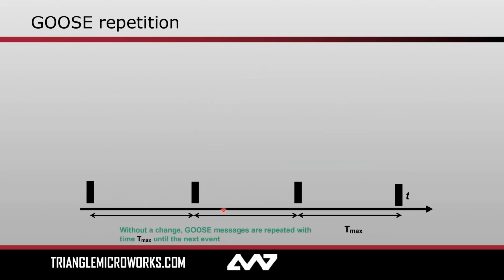Now let's dive a little deeper into what I mean by that repetition mechanism. There are two relevant parameters that you need to take into consideration if you're designing a system that uses GOOSE. One of those is Tmax and the other is Tmin. These both have to do with how fast or how slow the repetition will occur. Tmax is the max time during a steady state. Let's say that no changes have occurred in a while. No breakers have opened or closed, so their positions packaged into a data set are being repeated at this interval. And 5 to 10 seconds would be a common value for Tmax.